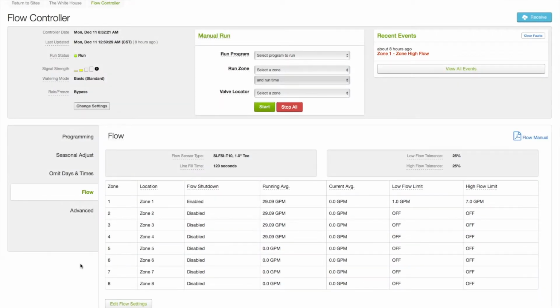Our controller's been running for a few days. Through the magic of video editing, we are going to look at the results. First, you can see that our high flow limit was set at 7 gallons a minute when our average has actually been 29 gallons per minute. So this resulted in a high flow alert. Now, what you need to know is that high flow alerts and low flow alerts are treated exactly the same. And that is, when one zone has a high flow alert, it shuts down that zone and that zone only.